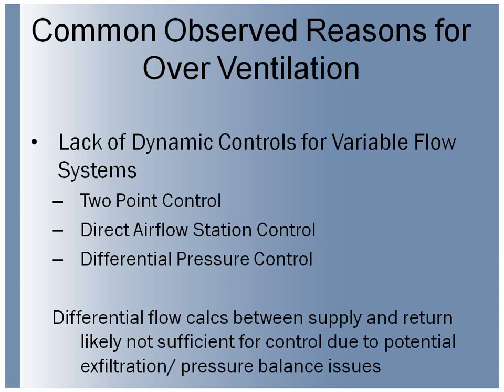The other one is a lack of dynamic control. So a lot of systems just simply never were specified to have any type of dynamic control of the minimum ventilation rates. There's a lot of ways to do it, either just a simple 2-point control. You could easily set up your system to modulate from one damper position to the other across the range of the supply fan as a coarse way of making the system have a dynamic response to the changing of the total volume flow of the system.